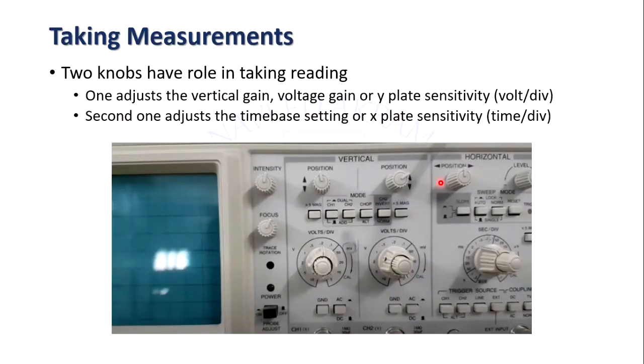For taking readings, there are two important knobs on the cathode ray oscilloscope. One adjusts the vertical gain — also called voltage gain or y-plate sensitivity. This is actually the volts per division along the y-axis. The second knob adjusts the time-based setting — also called x-sensitivity — and this is actually the time per division along the x-axis.